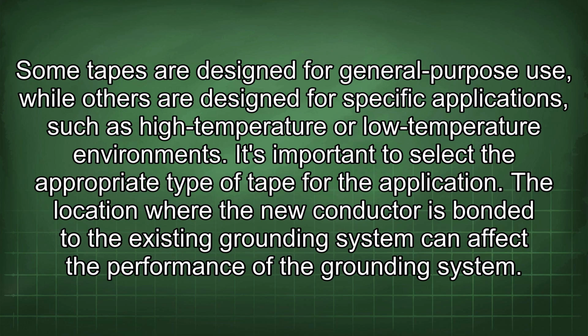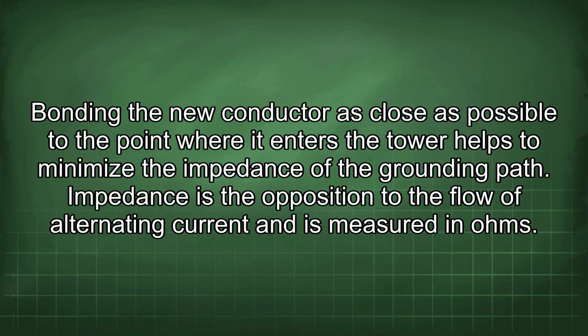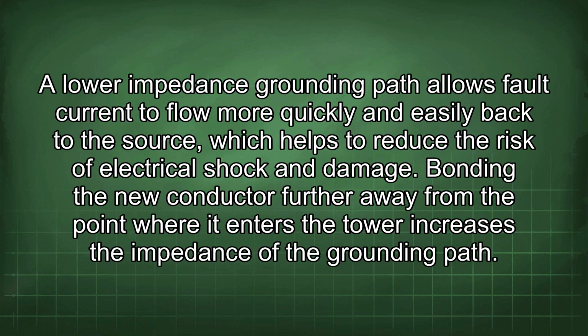The location where the new conductor is bonded to the existing grounding system can affect the performance of the grounding system. Bonding the new conductor as close as possible to the point where it enters the tower helps to minimize the impedance of the grounding path. Impedance is the opposition to the flow of alternating current and is measured in ohms. A lower impedance grounding path allows fault current to flow more quickly and easily back to the source, which helps to reduce the risk of electrical shock and damage.